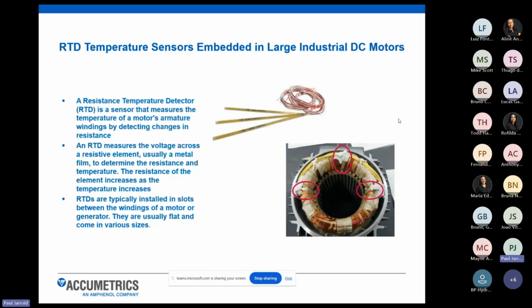So this is an idea of what most customers would embed or use inside of the big industrial motors. These are RTDs. Usually the most common ones we see are PT100 3-wire RTDs that are housed in these epoxy slots, basically, and those get installed inside the armature winding of the motor. And our system allows you to get access to that RTD sensor data.